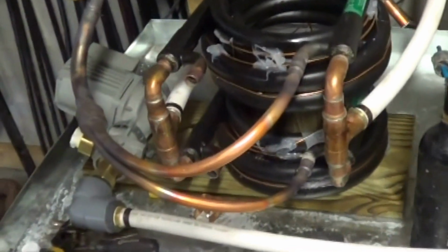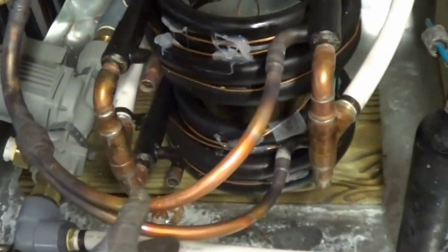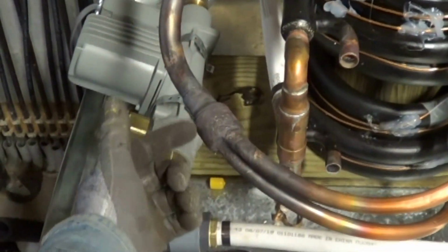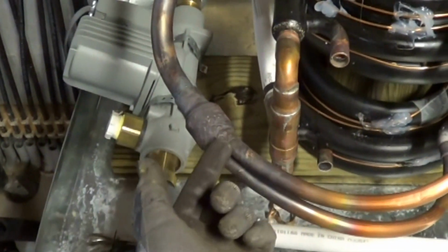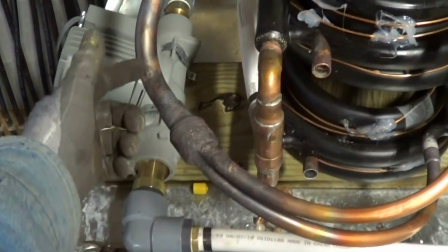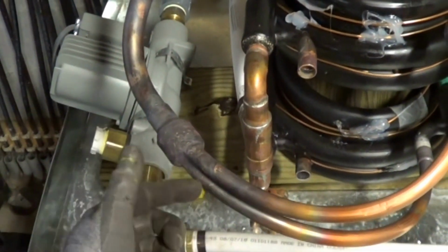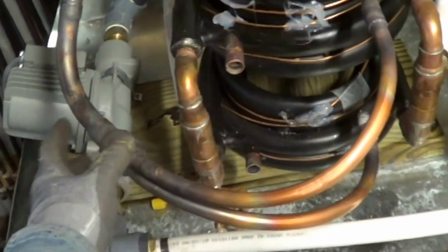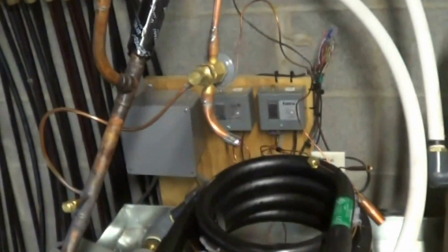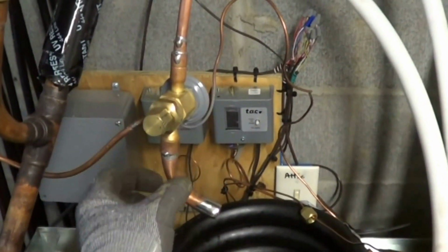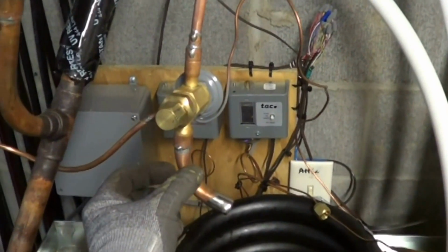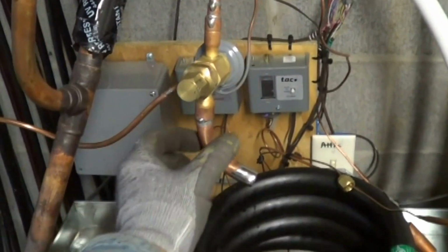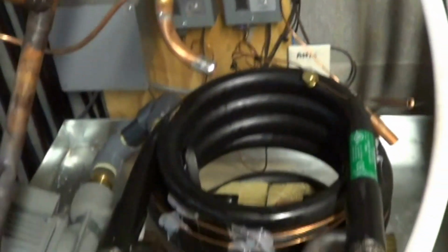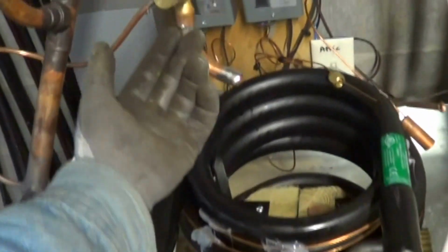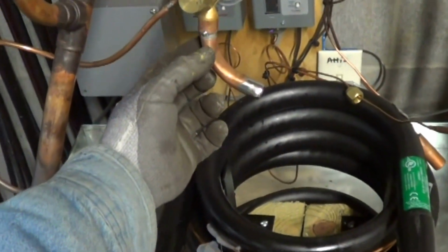So I'm repiping here. It's important that the flow is equal. So on hot gas, I'm not concerned about liquid, so these can be vertical. If this were the liquid line, all your liquid would go on the bottom circuit and gas in the top, which would be bad. So on the liquid line, I'm doing them vertical, and ideally you'd have a distributor, but they don't make a 2-circuit distributor because this is a 2-circuit system. So I'm going to make a distributor here.